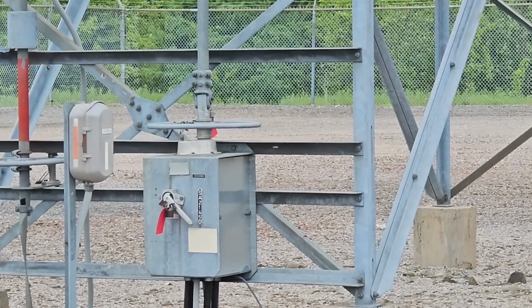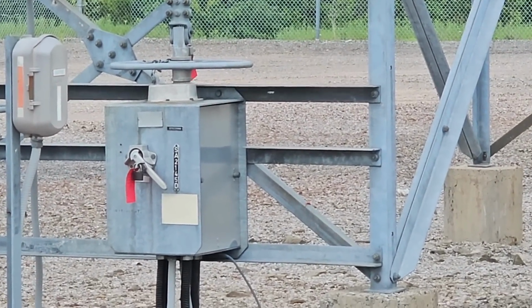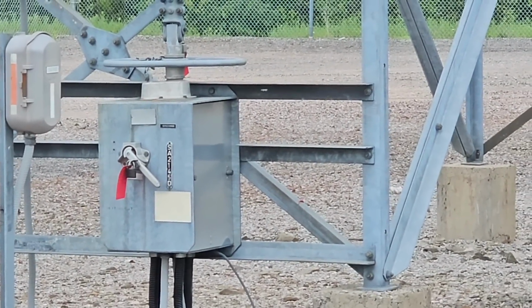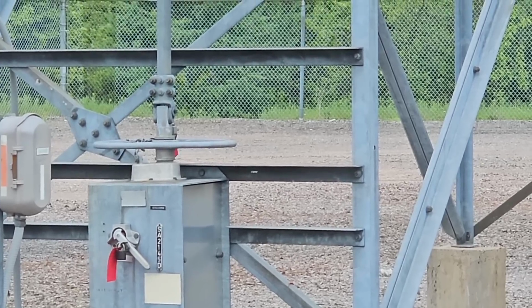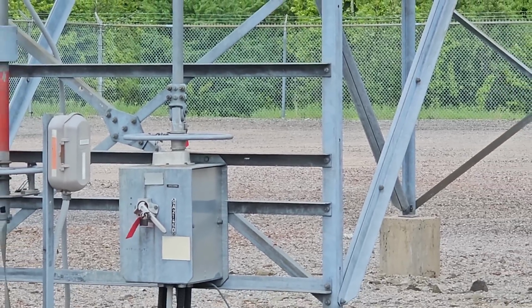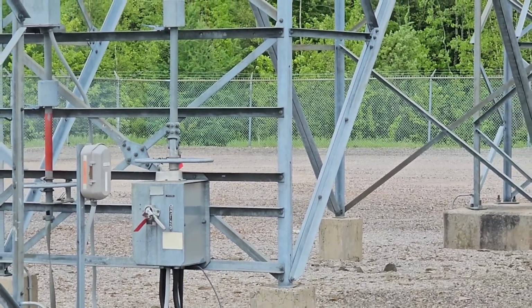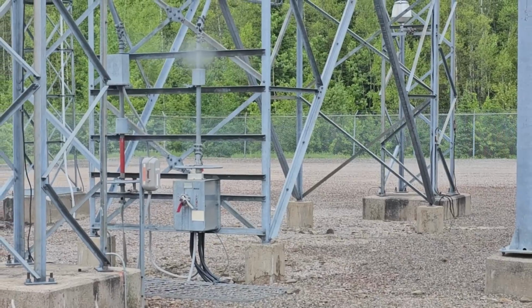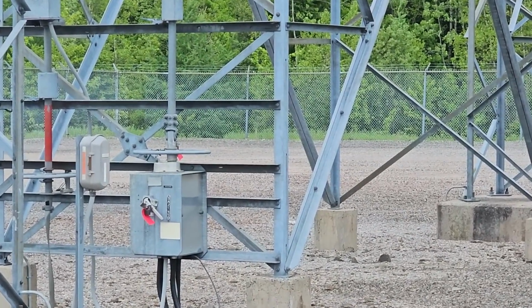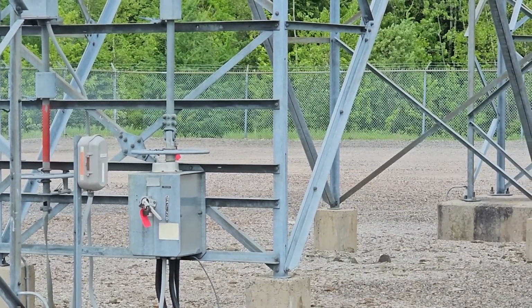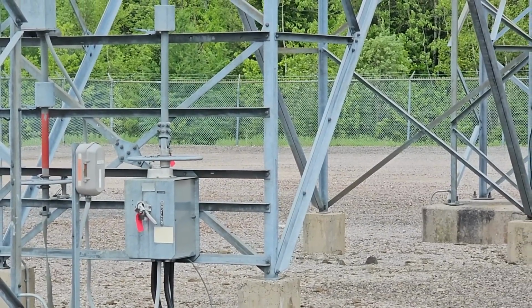One of my other steps was to, we call it decouple. So there's the motor that operates that switch. So I moved that handle over and locked the hand wheel. So if somebody remotely attempts to close that in while the guys are working on the line, it can't. It's physically disconnected, as well as that pipe where the hand wheel on it is also physically locked and chained up.